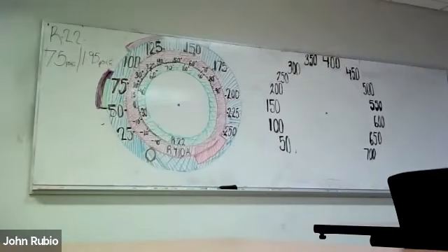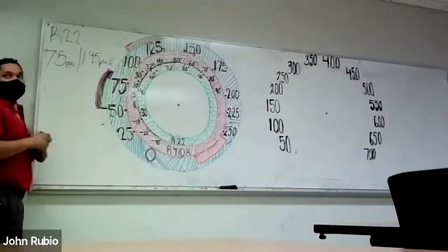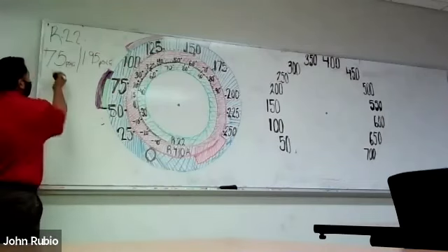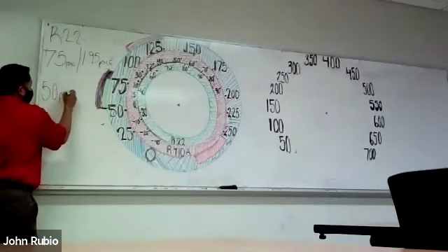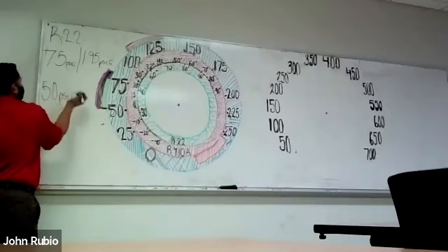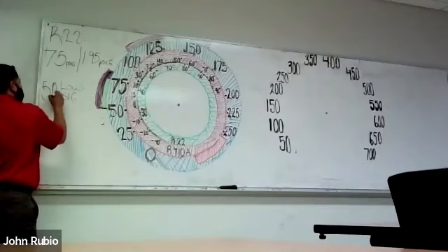We learned yesterday that when R22 begins to freeze up, it's because gauge pressure has fallen below 50 psig. When we're at 50 psig on the low side, that's when we begin to freeze up and make ice.